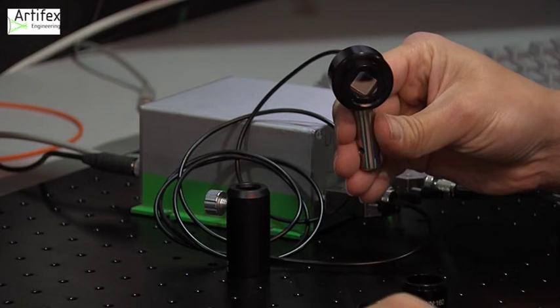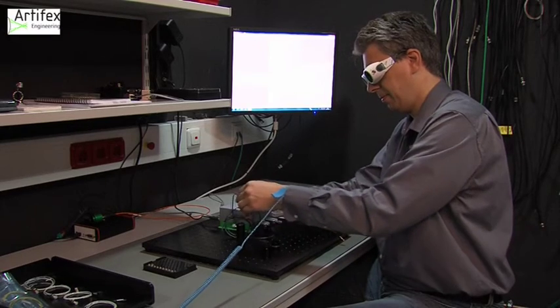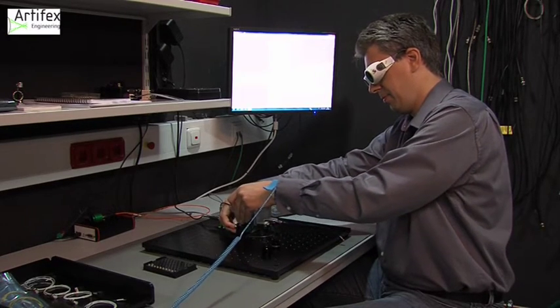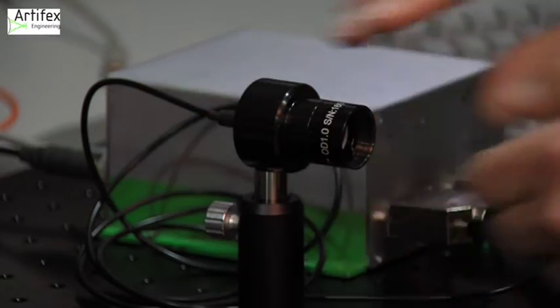The power detection channel uses the detector heads and integrating spheres from our OPM150 series of optical power meters. Calibrated filters extend the dynamic range of the device.